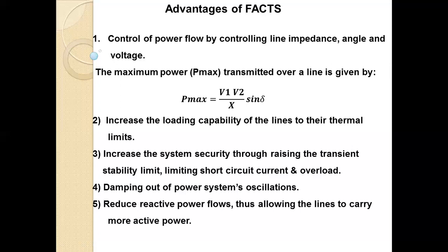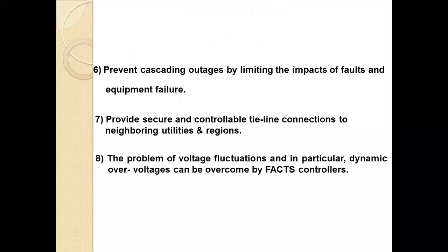The second advantage is to increase the loading capacity of the line to its thermal limit. Third, increase the system security through raising the transient stability limit, limiting short circuit current and overload. Fourth, damping out power system oscillation. Fifth, reduce the reactive power flow, allowing the line to carry more active power. Sixth, prevent cascading outages by limiting the impact of faults and equipment failure. Seventh, provide a secure and controllable tie line connection to neighboring utilities and regions. The problem of voltage fluctuation, and in particular dynamic overvoltage, can be overcome by FACTS controllers.